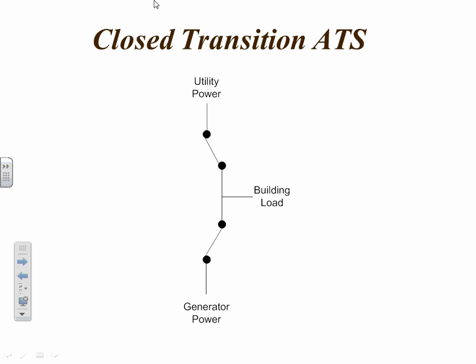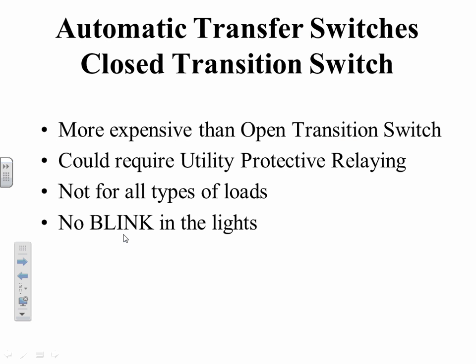In the closed transition, what we're doing is we're actually picking up another pivot point. So this one pivots between connected and open. Same thing here, connected and open. But I've got two pivot points, one here and one here. And building load is connected to that. So a closed transition switch is more expensive. It could require utility protective relay. In most instances, it does. Most utilities do. But they're getting a little more lax on this.